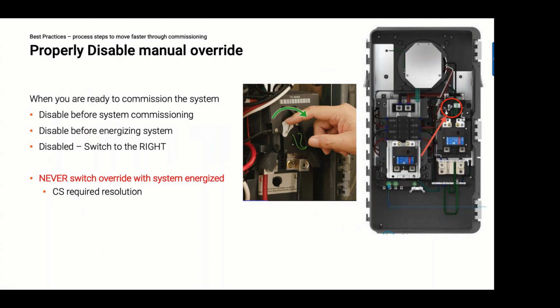Next best practice is about the manual override. I think most of you know this already, but I want to remind you that the system controller comes with a manual override in the override position. That's the left position. So this manual override is shipped in the override position, and there's reasons why we do that. I won't cover that right now. But when you go to commission the system, the bottom line is you have to remove the system override from the override position, which is on the left side, and flip the switch to the right. And that's the picture of the hand here pulling the override switch down.